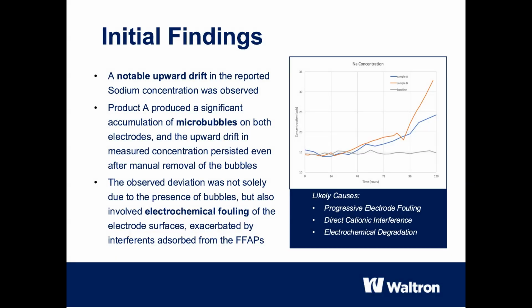The initial results of this new series of tests were immediately alarming. As the graph shows, we observed a significant upward drift in the measured sodium concentration for both tested products, from a baseline of 15 ppb to over 24 and 32 ppb respectively within 120 hours. In particular, with product A, we observed a significant accumulation of microbubbles on the electrodes. Interestingly, the upward drift persisted even after we manually removed these bubbles. This could indicate that the problem lies deeper than a purely physical blockage. We spoke with the FFAP manufacturer, who was surprised to hear about those microbubbles accumulating on the sensors.